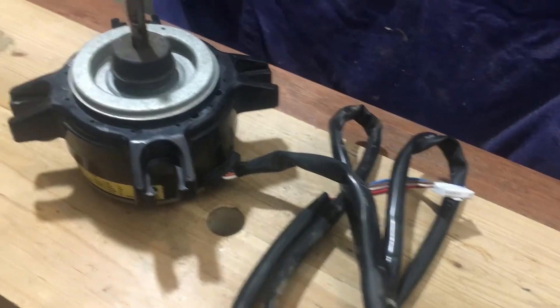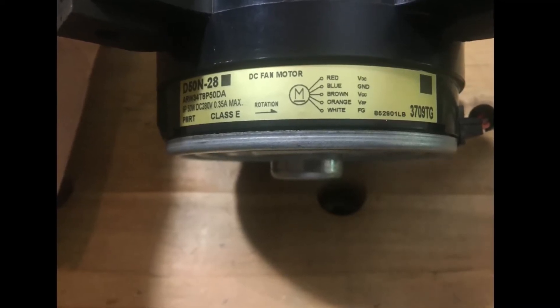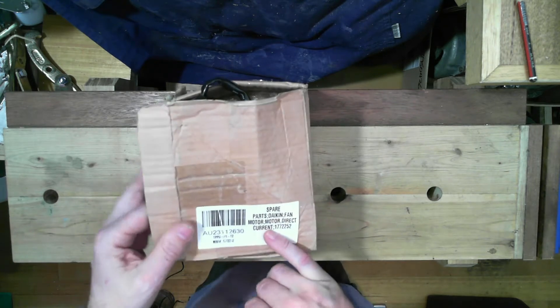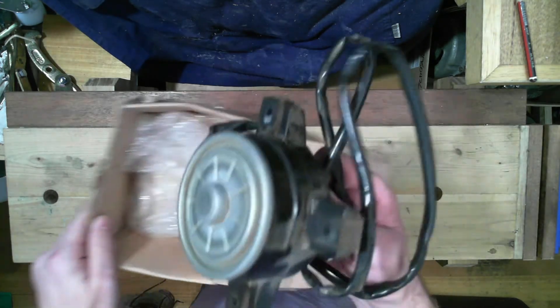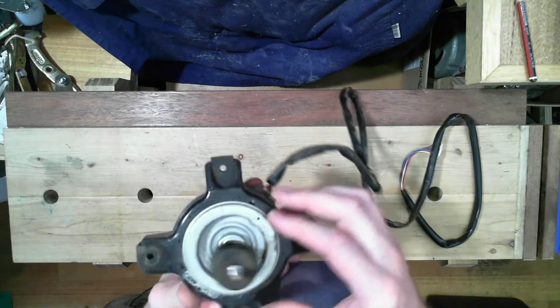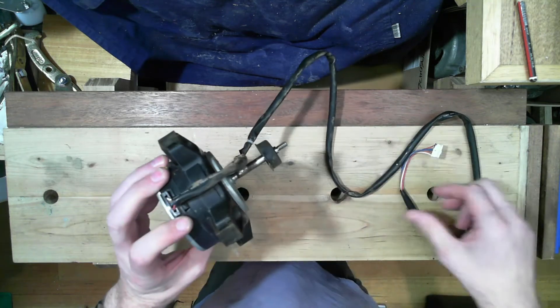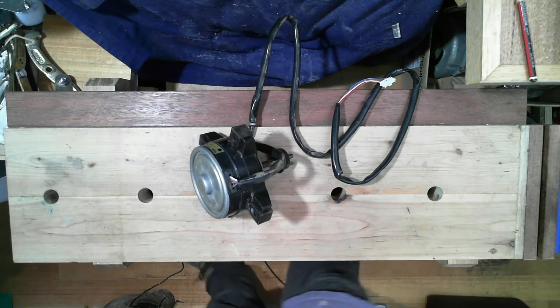Today I'm going to tear down this Daikin fan motor and see what's inside. On the mini workbench we've got a Daikin fan — it's a DC motor and it was a replacement. It went into our air conditioner and I'm curious about what's inside. The motor had in fact failed, and you can test that by checking the resistances. There's a particular test sequence that Daikin specify. But let's open this up.